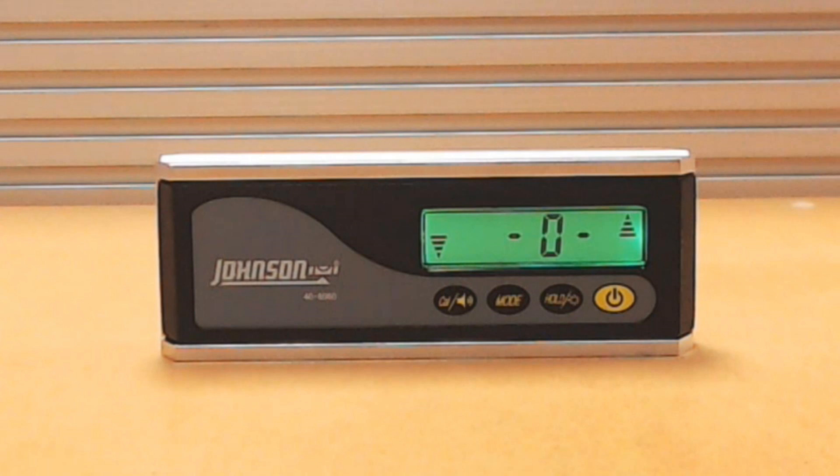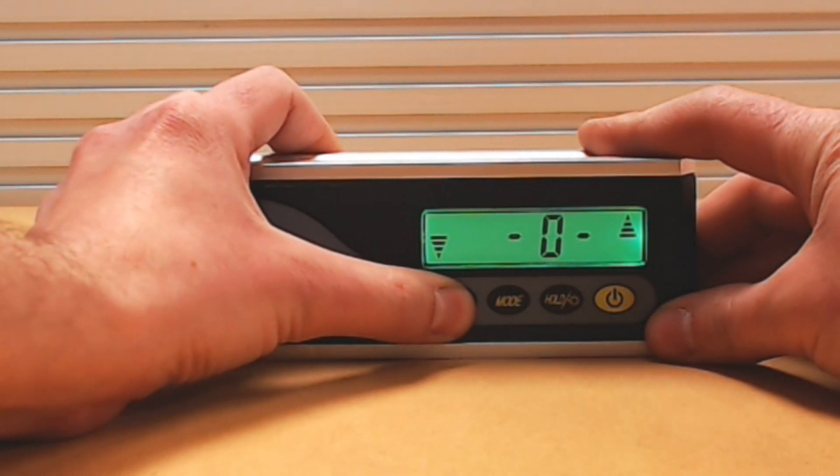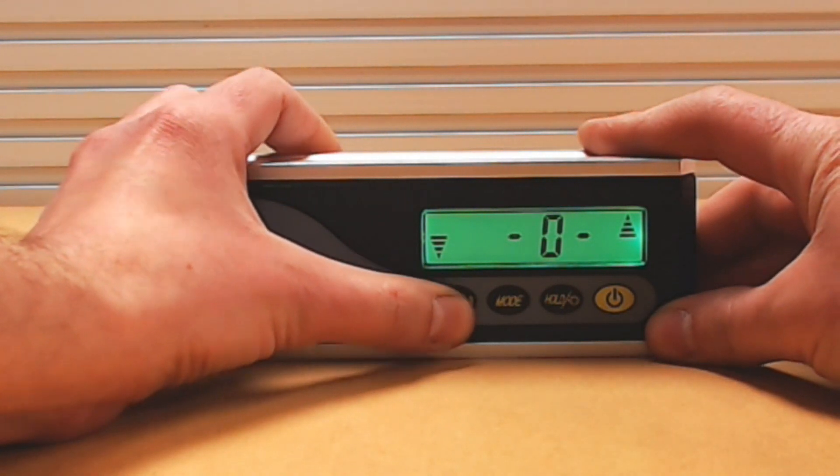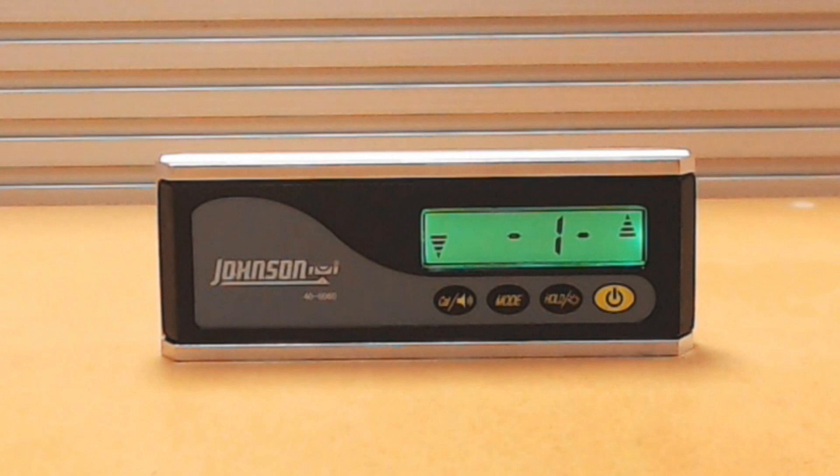Place the inclinometer on the clean reference surface and count out 10 seconds without moving the inclinometer so the angle reading has plenty of time to stabilize. Press the calibration button and the symbol 1 will appear on the screen. This indicates that the position one reading has been recorded into memory.